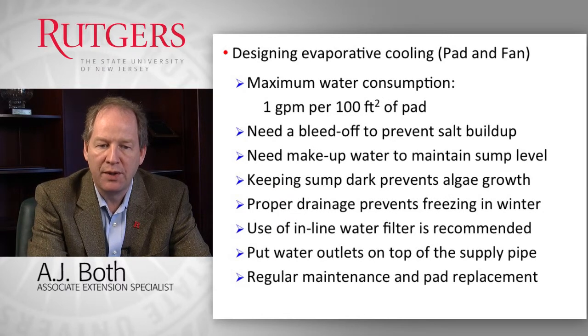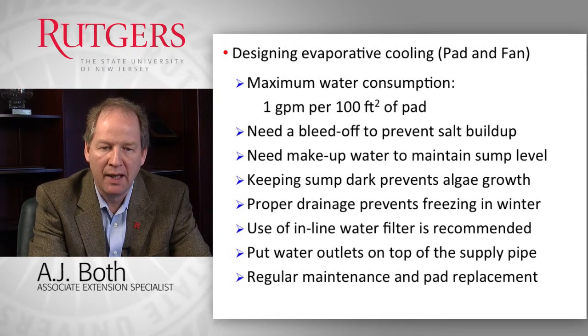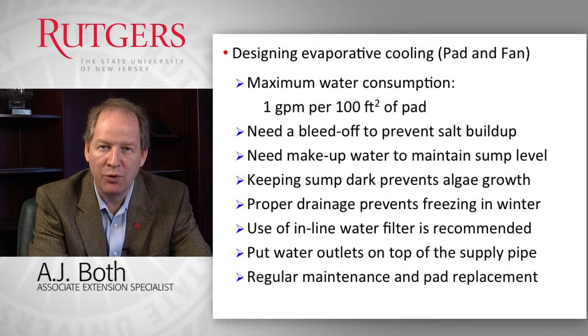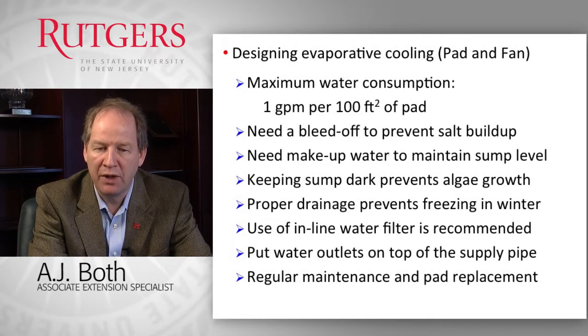If you want to know the maximum water consumption — to have some idea of how much water you need to provide to an evaporative cooling system — as a rule of thumb you can use one gallon per minute per every 100 square feet of pad area. This number will change depending on conditions; if you are in a desert environment where the air is very dry, that number may be higher. But as a first approximation, one gallon per minute per 100 square feet of pad area is a good starting point.